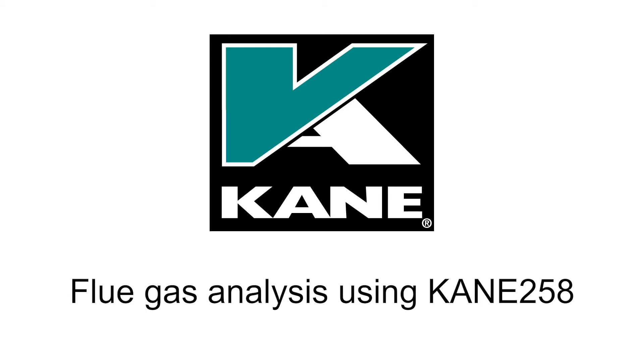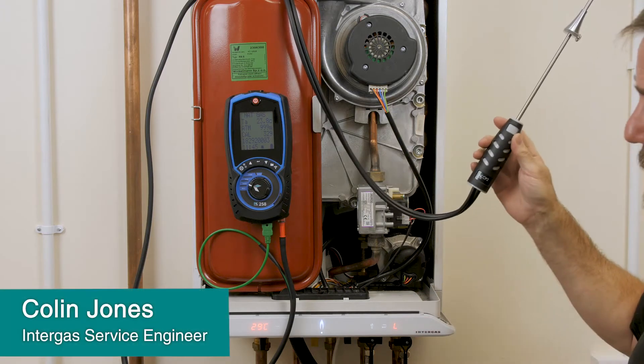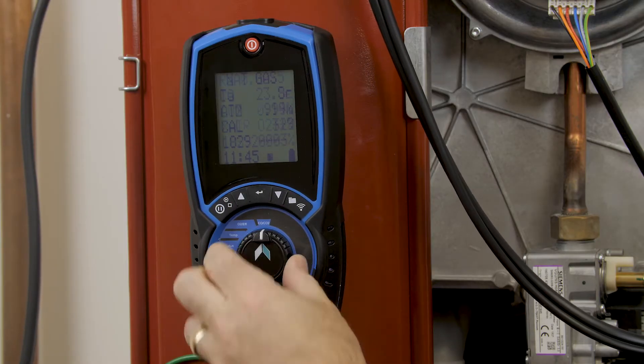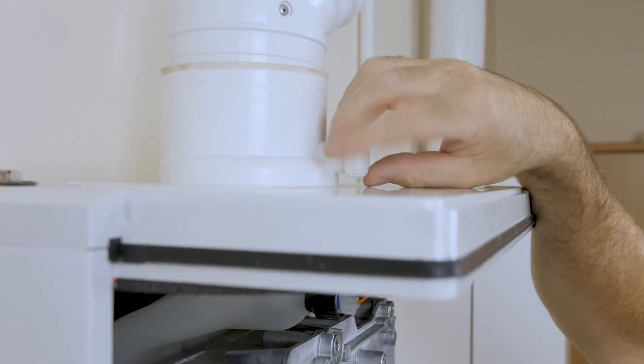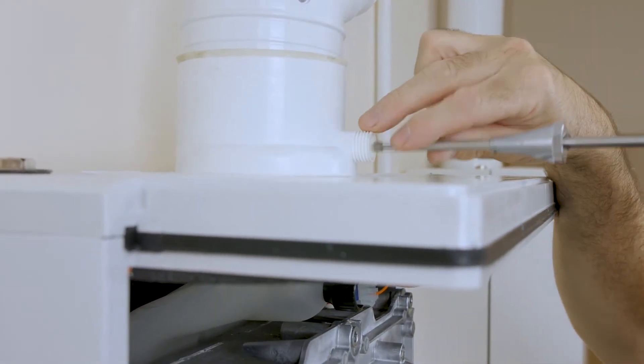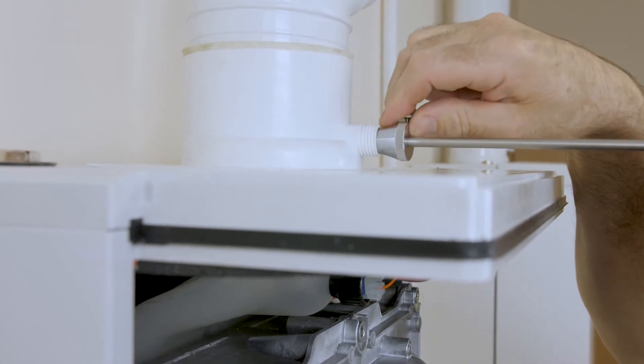Flue gas analysis, case off, two readings. Put the boiler into low fire. We're going to select our machine into CO2, remove the test cap and insert your probe to ensure a snug fit.